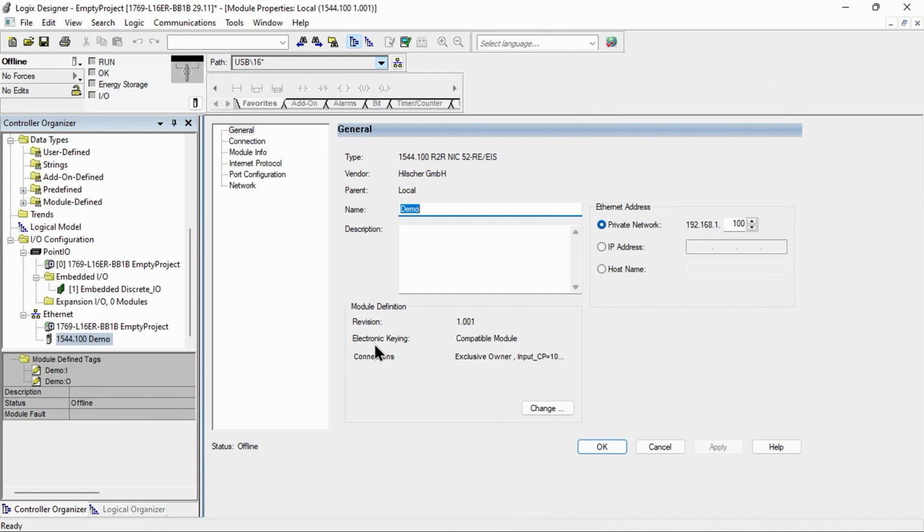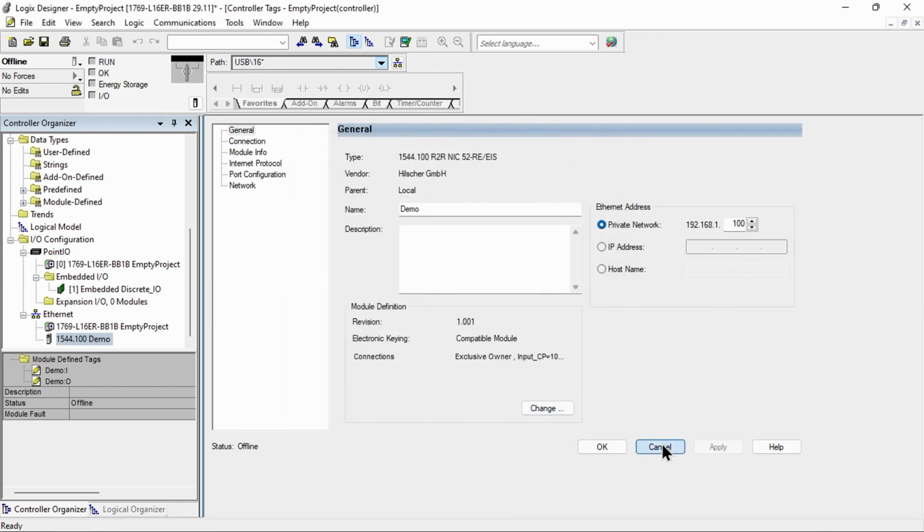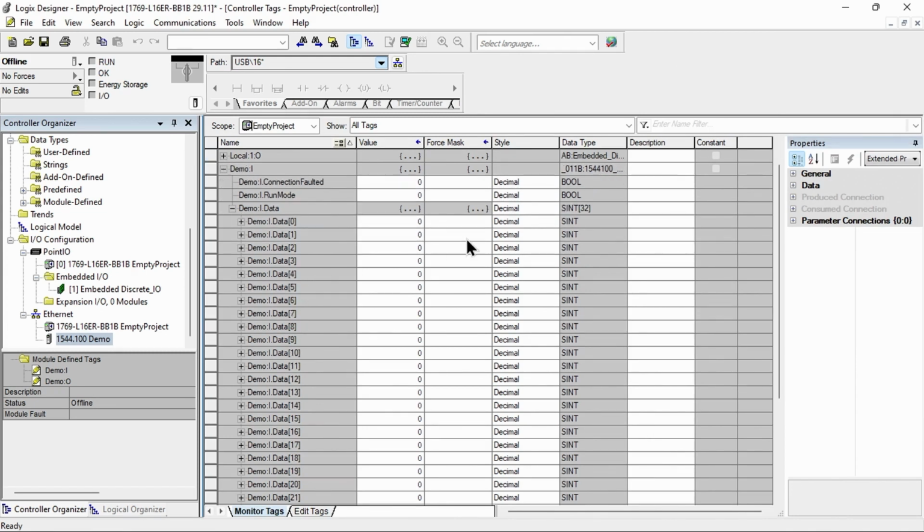Another common mistake is to forget to change the size of the variable from SINT to INT. In that case, the variables that are automatically created when you add the device will be of the wrong size, so they will be 8-bit variables or short ints. And in case you are using our AOI instruction, this variable will not match the size that the AOI instruction is expecting, so the AOI won't work. Also, if you decide to do your own conversion of the register into the real variables, this won't match our documentation, so it'll make your life a little bit harder.